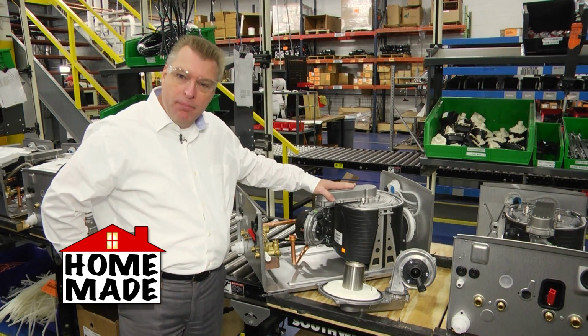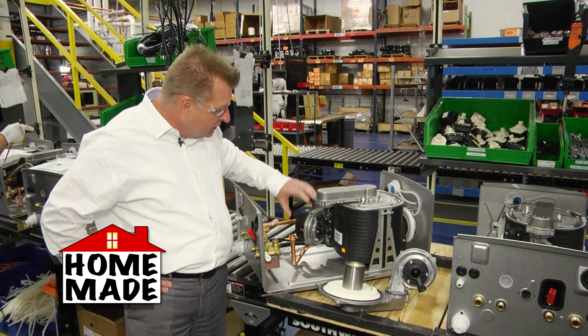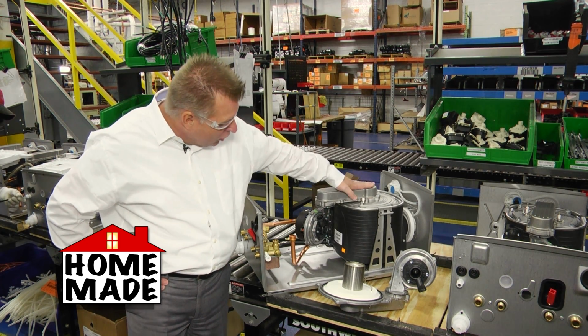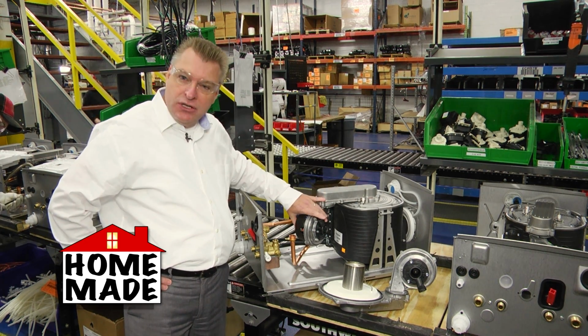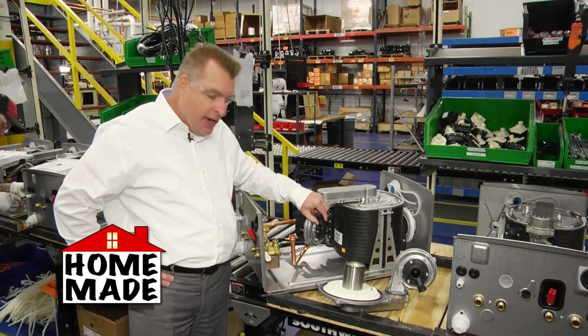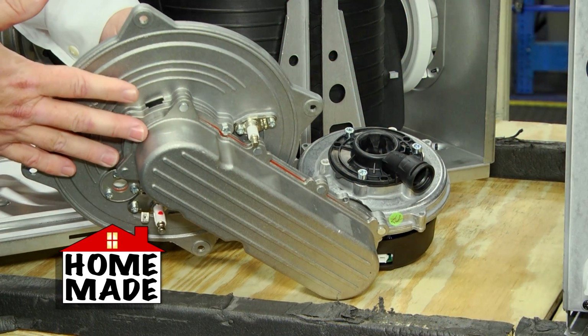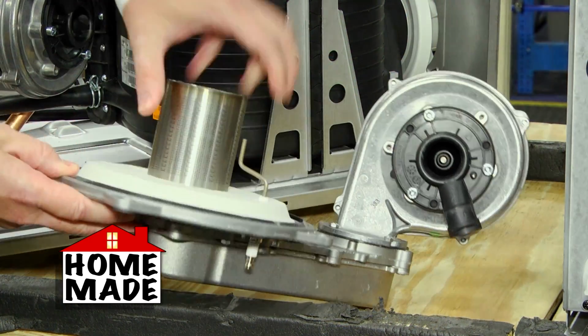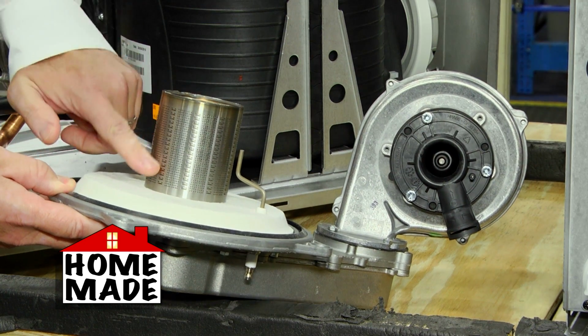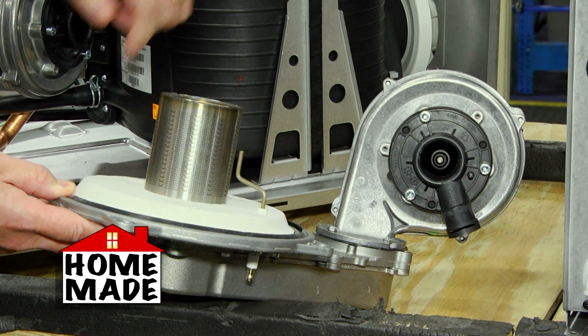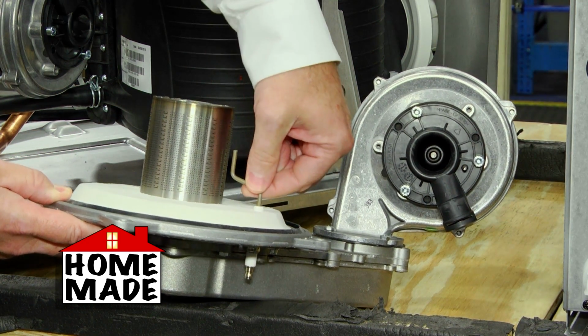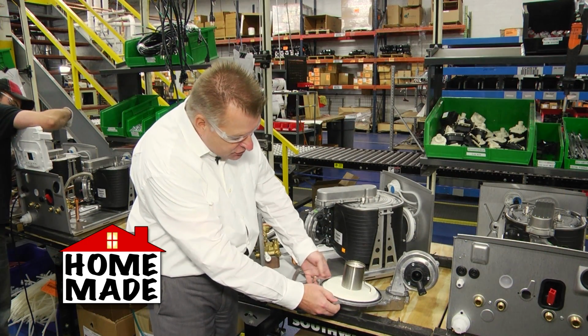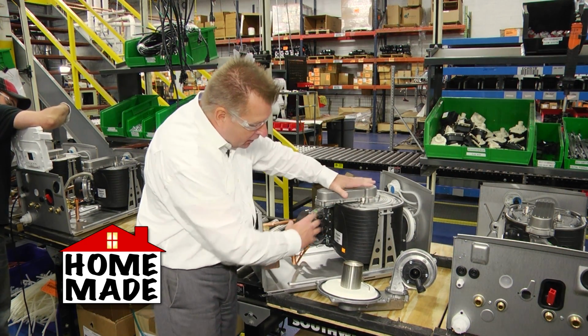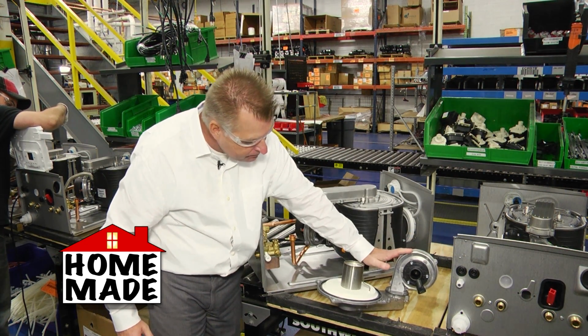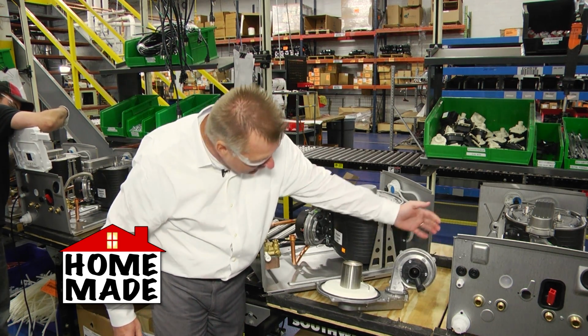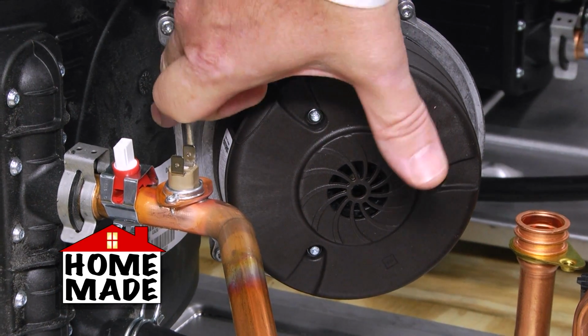Now the next most important part for this boiler is actually the blower and burner assembly. This device here takes the inlet of gas, whether it's natural gas or propane, draws in outside air and mixes that gas and air, and then it's ignited inside the heat exchanger to produce the heat. So overall what you have here, this assembly is actually right here. This is basically your blower assembly. Your gas goes in here, and then it draws in air on the other side of the blower.